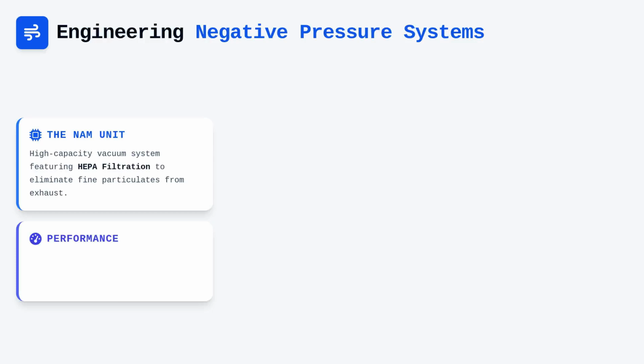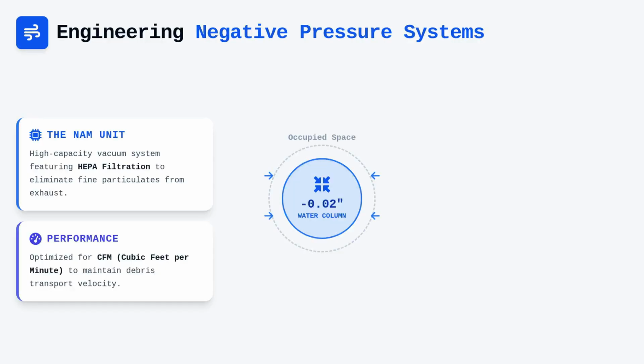The efficiency of this system is governed by the ability to move a specific volume of air, measured in cubic feet per minute, at a velocity sufficient to transport the debris through the vacuum hose. We generally target a minimum of minus 0.02 inches of water column relative to the surrounding occupied space to ensure that any leaks in the containment or ductwork result in air entering the system rather than debris exiting it.